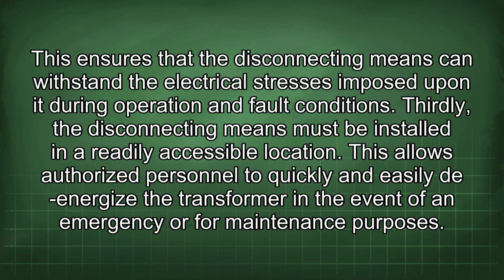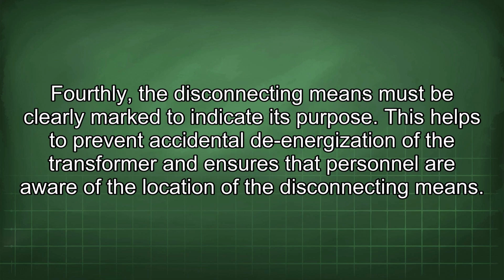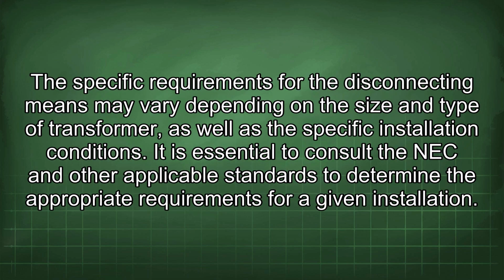Thirdly, the disconnecting means must be installed in a readily accessible location. This allows authorized personnel to quickly and easily de-energize the transformer in the event of an emergency or for maintenance purposes. Fourthly, the disconnecting means must be clearly marked to indicate its purpose. This helps to prevent accidental de-energization of the transformer and ensures that personnel are aware of the location of the disconnecting means. The specific requirements for the disconnecting means may vary depending on the size and type of transformer, as well as the specific installation conditions. It is essential to consult the NEC and other applicable standards to determine the appropriate requirements for a given installation.